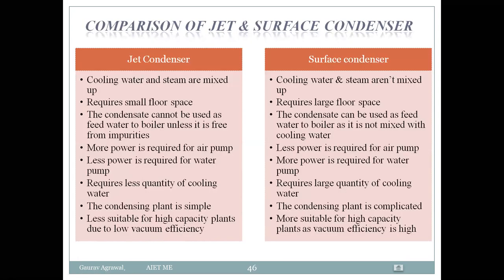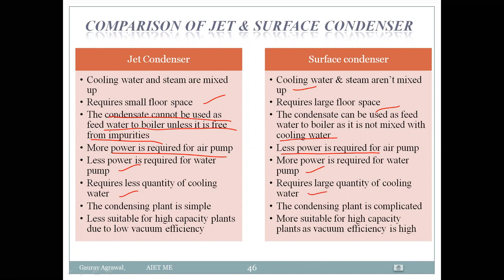Here is a comparison between surface condensers and jet condensers. In jet condensers, cooling water and steam are mixed directly; in surface condensers, they are not. Jet condensers require a small floor area; surface condensers require a large floor area. Condensate from jet condensers cannot be reused as boiler feed water unless free from impurities, whereas in surface condensers it can be reused. Jet condensers require more power for the air pump; surface condensers require less. Jet condensers need less cooling water; surface condensers need more. Jet condenser construction is simple; surface condenser construction is complex due to the use of separate tubes. Surface condensers are preferred for high capacity plants.